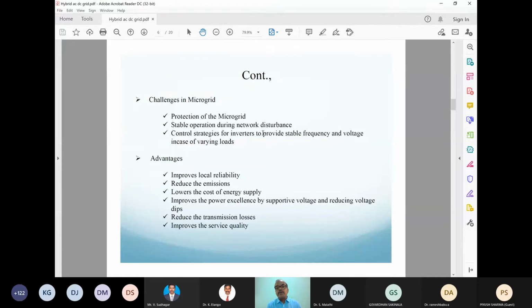Disturbances can happen due to faults, over-voltage, or other abnormalities. There are two kinds of studies in the power system: steady state analysis and transient analysis. Transient analysis is required once an abnormality happens, while steady state analysis applies to normal conditions. Load flow analysis is essential in both normal and abnormal conditions, but transient analysis and short circuit analysis are required only during transient or abnormal conditions.